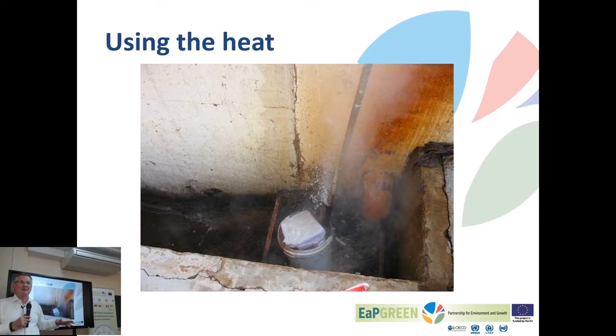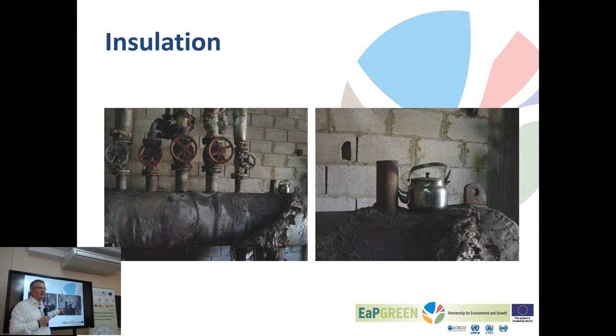This is a steam manifold distributing steam. This is about 4 meters long, half a meter in diameter. Heat losses here were a little bit more than 30 kilowatts. Insulating these pays back in half a year. Again, the operators were well aware of the heat escaping from this manifold. They prepared their tea on this manifold.